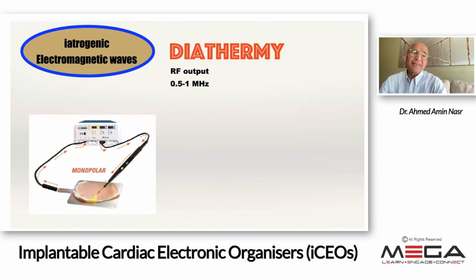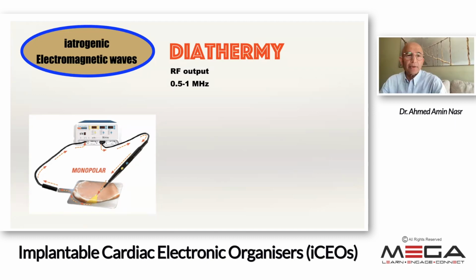However, the exit of these waves is the diathermy pad. And you can see the yellow cone between the inlet and the exit, very wide, if you can imagine that on a human body. And that would increase the likelihood of interference with the pacemaker. So it is really too noisy.